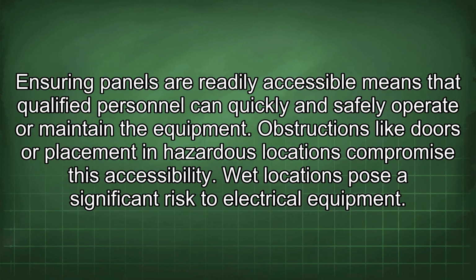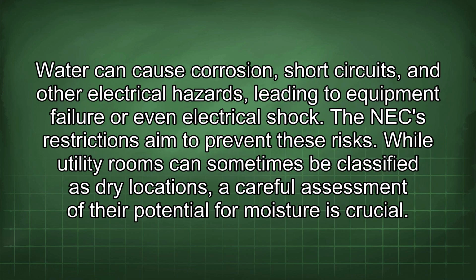Ensuring panels are readily accessible means that qualified personnel can quickly and safely operate or maintain the equipment. Obstructions like doors or placement in hazardous locations compromise this accessibility. Wet locations pose a significant risk to electrical equipment. Water can cause corrosion, short circuits, and other electrical hazards, leading to equipment failure or even electrical shock. The NEC restrictions aim to prevent these risks.